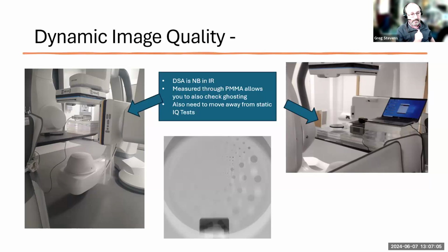So we will need a new image quality test object that is far closer to what the clinicians are seeing, or the material that the clinicians use. So obviously some sort of PMMA, but the idea of using these hard metal objects is really a no-no, and you can't have a lot of them in the system. I've also put in little plastic pipes and squirted some contrast through there, and I don't get the same ghosting effect. So I'm not entirely sure. There's obviously some active image processing going on.